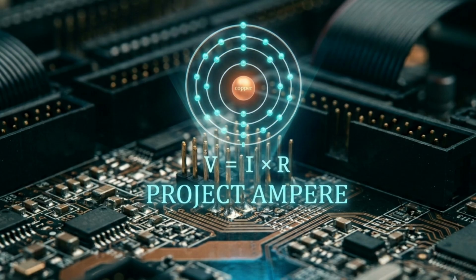75, maybe even 80 amps. Slamming through that tiny switch the exact instant the contacts touch. And I just installed a 10-amp switch. Exactly. You just hit a 10-amp component with an 80-amp hammer. The contacts will pit, they will erode, or like we discussed earlier, they will spot weld shut. So the switch fails, the light stays on, or worse, the switch overheats and literally melts the panel.